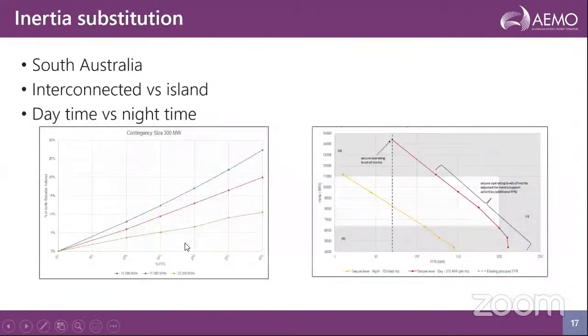The next application is about the inertia substitution. So we as AEMO use the battery for inertia substitution, particularly for South Australia, where we have developed a relationship between FFR, the fast frequency response, and inertia requirement, as shown on the right side of the figure. Indirectly, we are substituting some portion of inertia with FFR and still meeting the system security requirement.